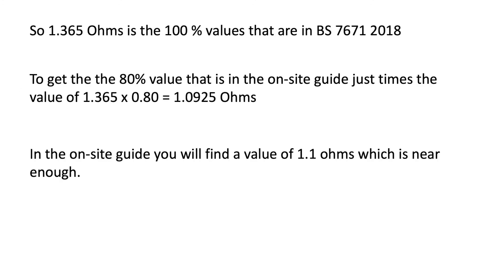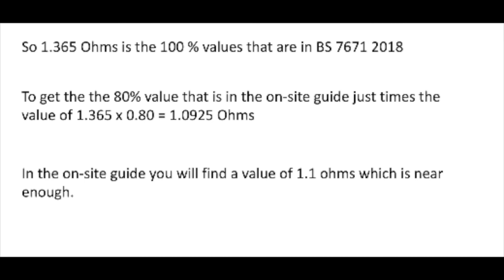So 1.365 ohms is the 100% value that's in BS 7671 2018. To get the 80% value that's in the on-site guide, you just times the whole thing by 0.8 - 1.0925 ohms. In the on-site guide you'll find a value of 1.1 ohms which is near enough.